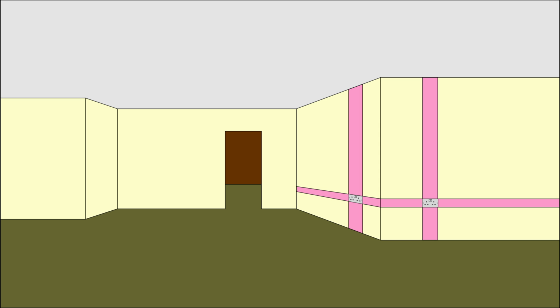In this case, I'll say we could either put them horizontally or vertically. If this had concrete floors, then putting it through the walls would be a good choice. But if it was, say, suspended floors or floorboards or whatever, it'd be far more sensible just to put the cables, say, up to each socket from underneath, and then just put the cables under the floor. Because of course it's much easier to take up a couple of floorboards than it is to start cutting out whole chunks of wall for tens of meters.